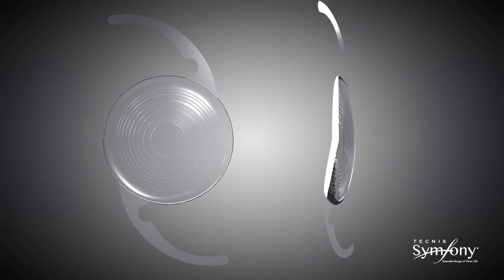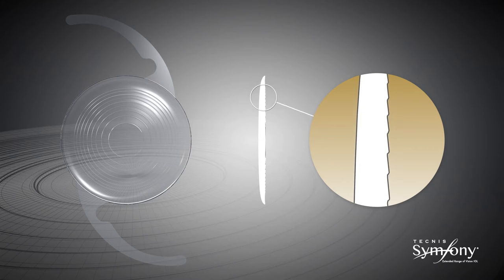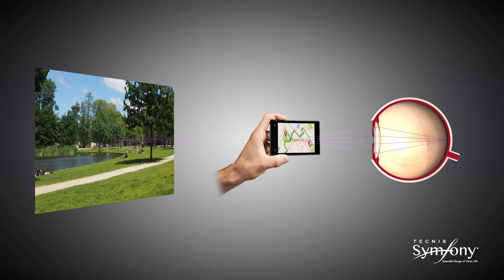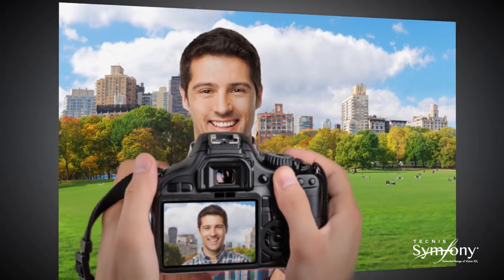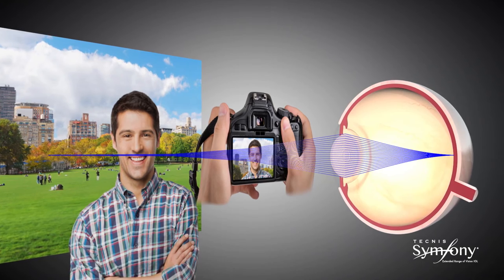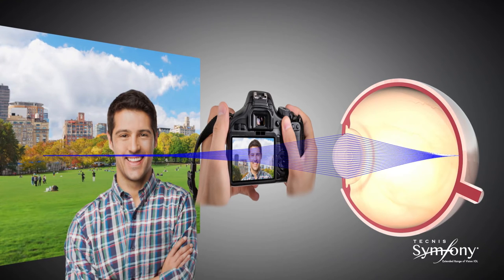Light can be distributed in almost any desired way by modifying the Echelette design of the diffractive lens. The Echelette is the relief or profile of the lens, meaning its height and shape within each ring. The design of the Echelette determines how the light is transmitted through the lens. In multifocal IOLs, diffractive technology transmits the light in such a way that it converges at more than one focal point. The Tecnis Symfony diffractive lens technology is optimized to transmit light over a range of distances — this is called constructive interference and results in an elongated focus.